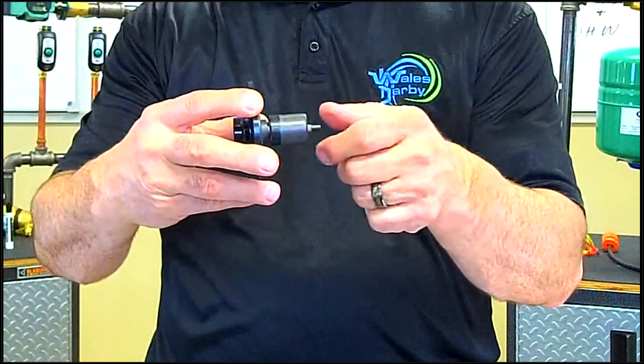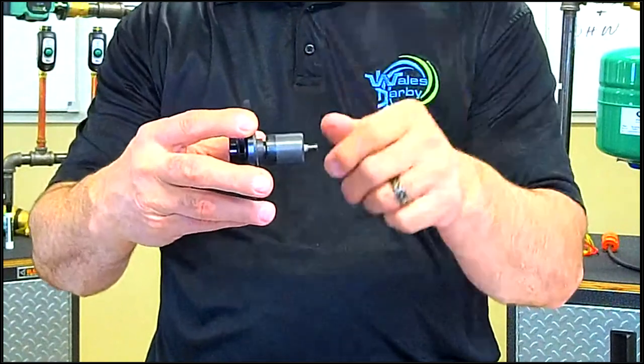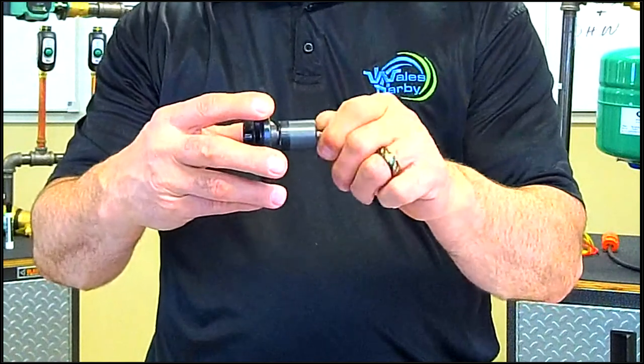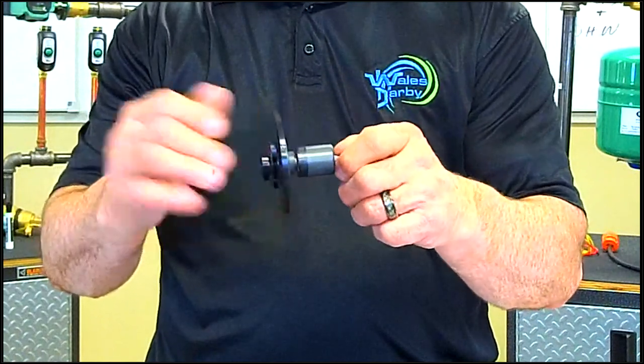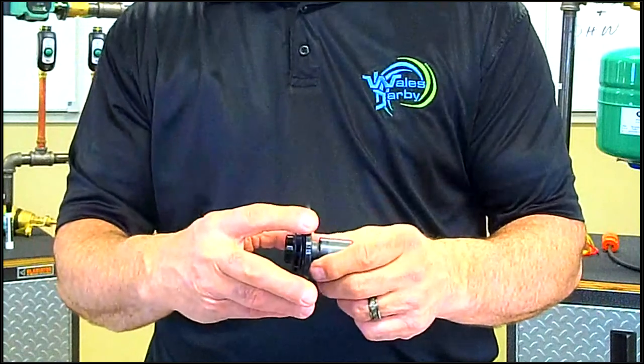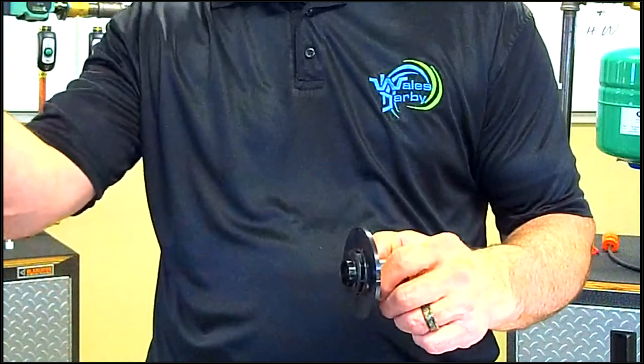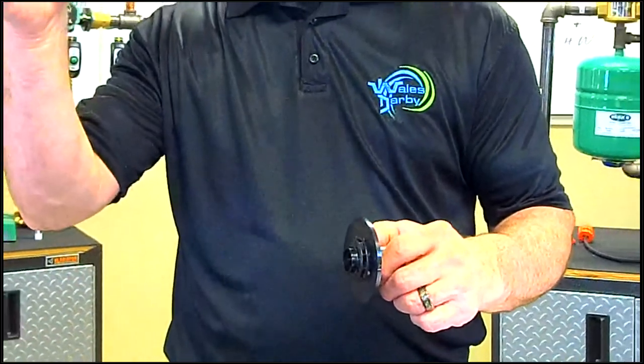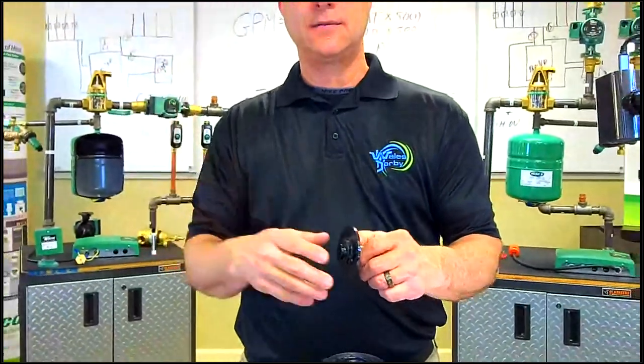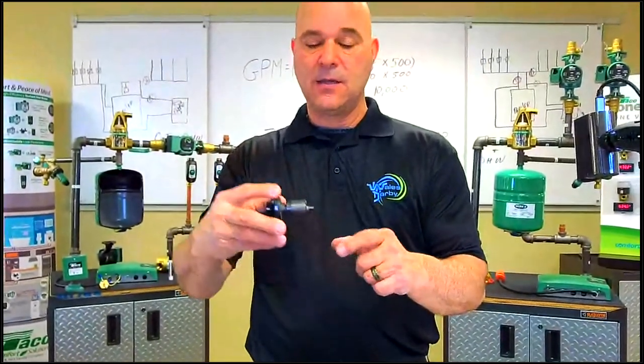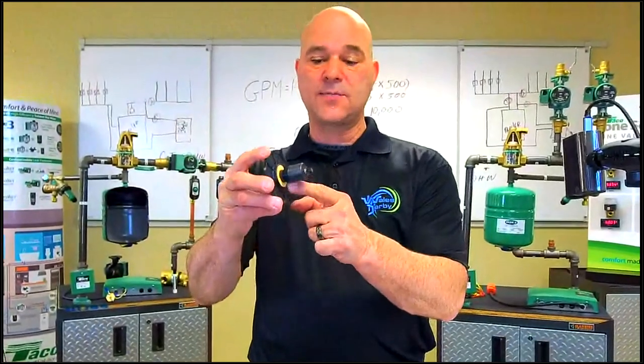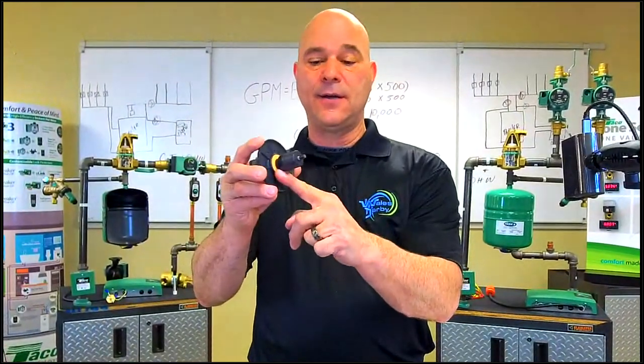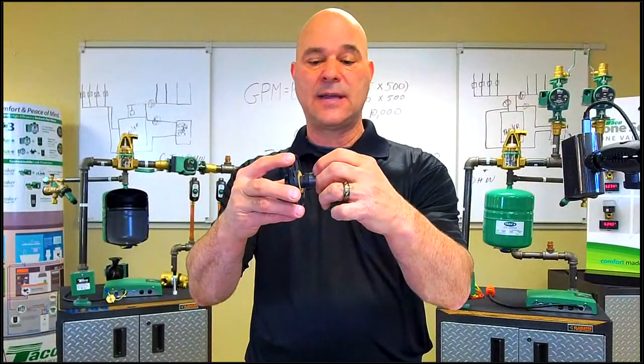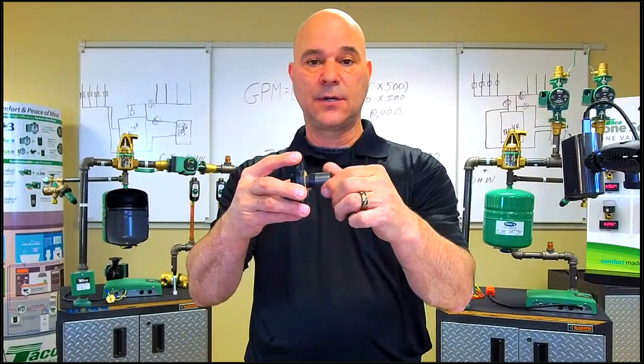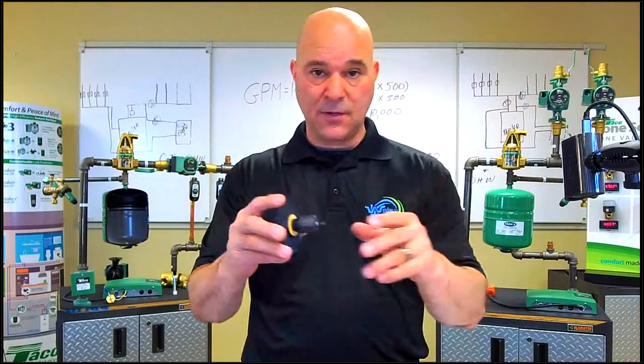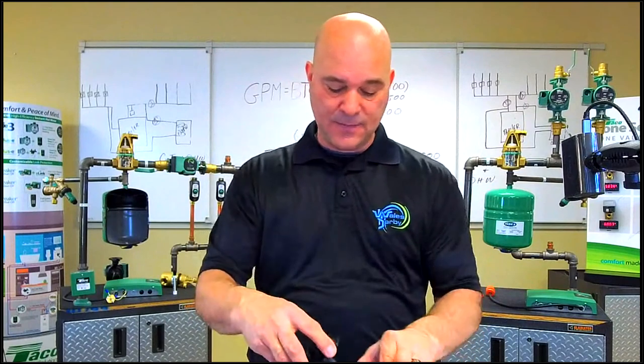If anyone on the call has been in the industry as long as I have, we used to run around 20, 25 years ago with a little ball peen hammer in our toolbox. When there was a seized circulator, you would tap on the side of it and that would break the black iron oxide loose and get that motor to rotate. Well, Taco has put a black iron oxide barrier here so that those metallic pieces cannot get to this rotor. And we're the only one in the game that's doing that.